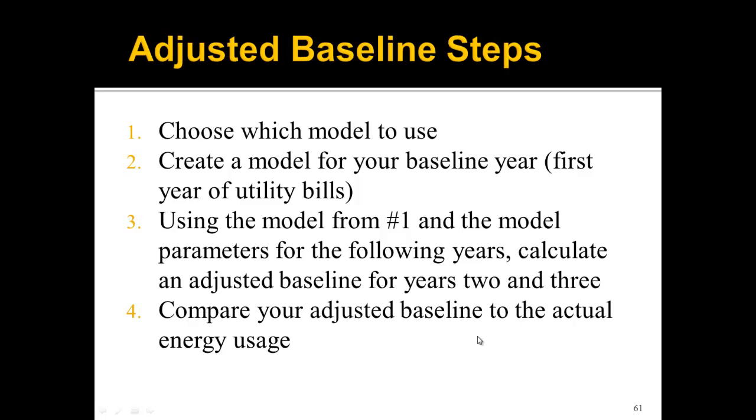Let's think about adjusted baseline with four steps. First, you're going to choose which model to use. The second step is create a model for your baseline year, and that baseline year is going to be the first year of utility bills that you have. Then using the model from number one and the model parameters for the following years, calculate an adjusted baseline for years two and three. Once you have an adjusted baseline, that's basically like your weather adjusted energy usage. You're going to compare it to the actual energy usage. Then you can compare apples to apples, because you eliminated the varying weather.